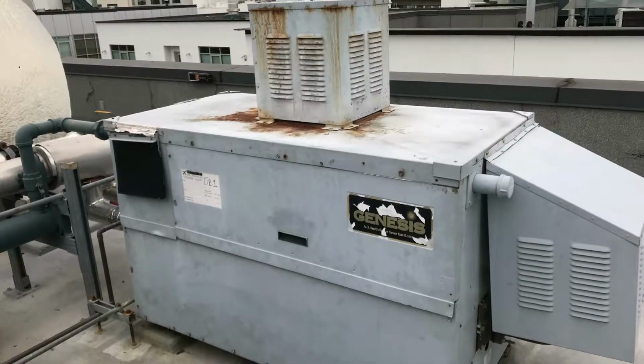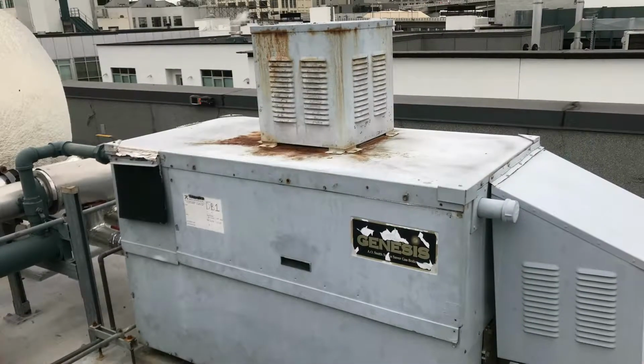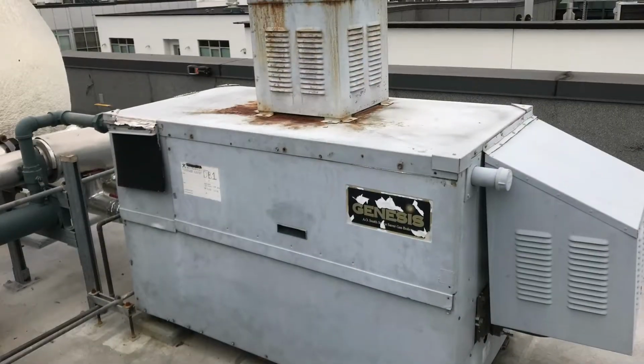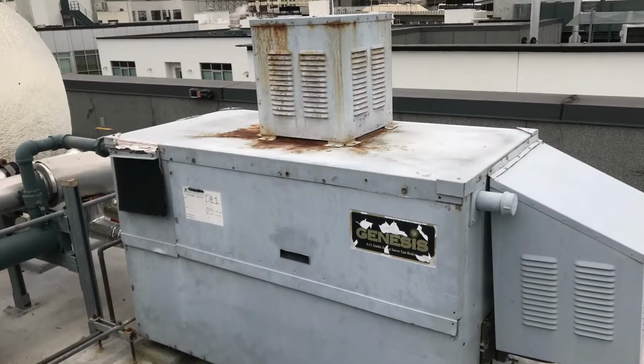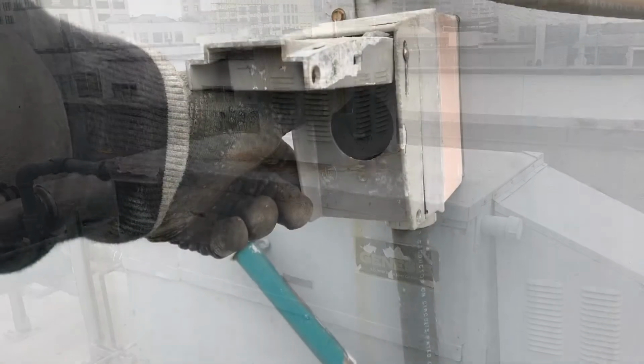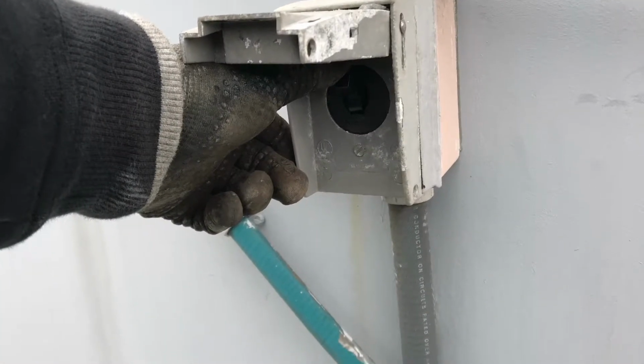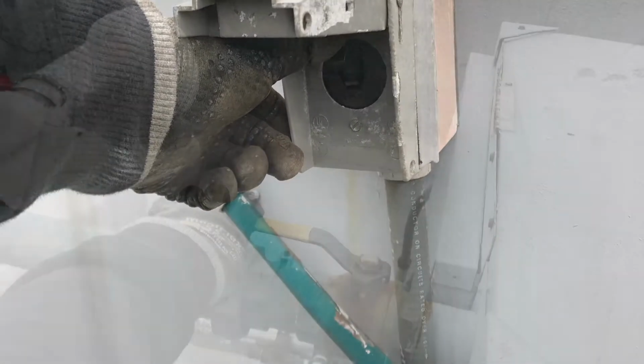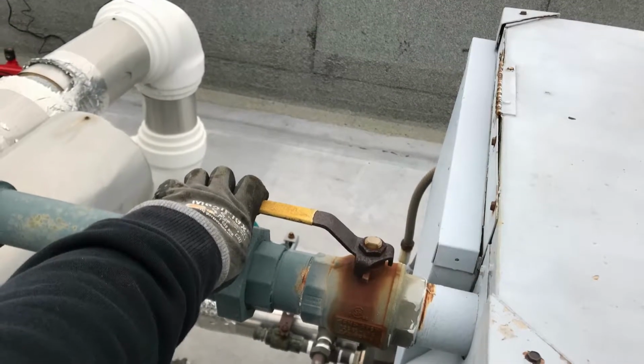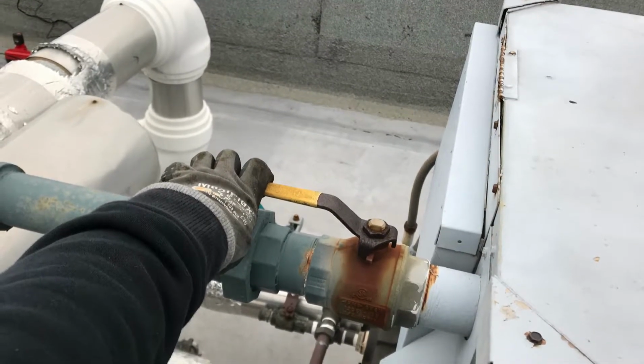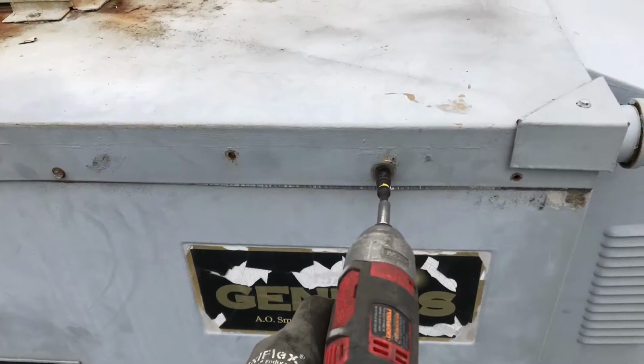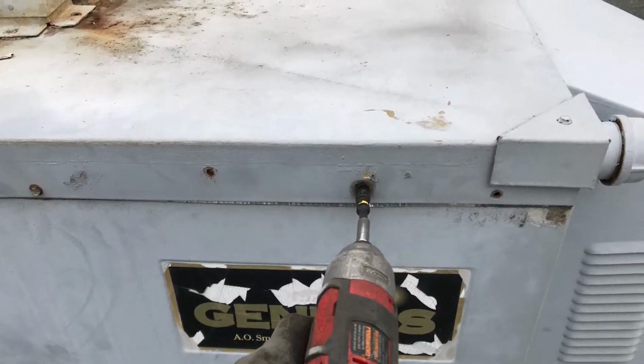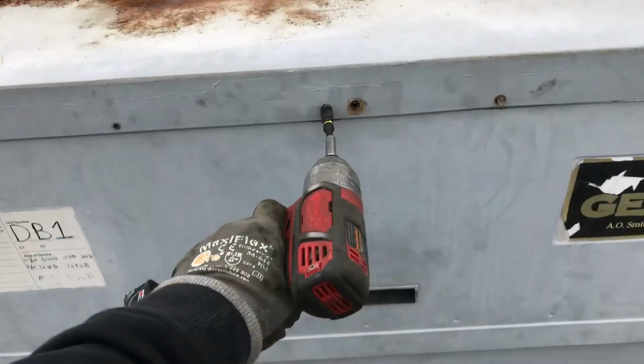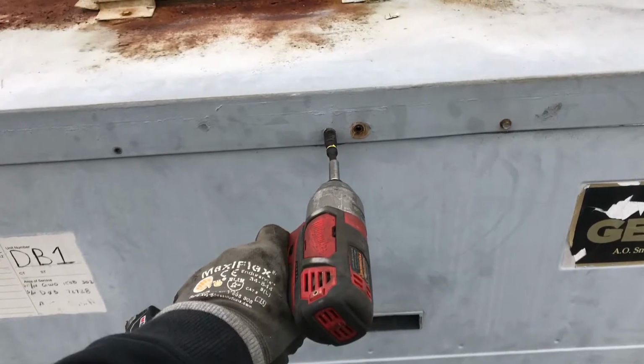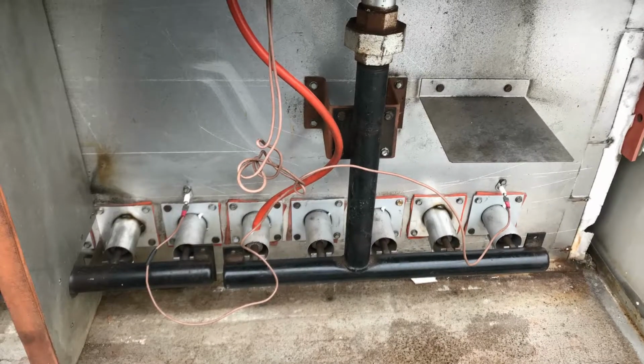This video explains to you how to clean the heat exchanger on a forced draft boiler, similar to this A.O. Smith. First, kill the power. Shut off the gas. Unscrew the top and bottom panels to expose the blower section and the burner section.